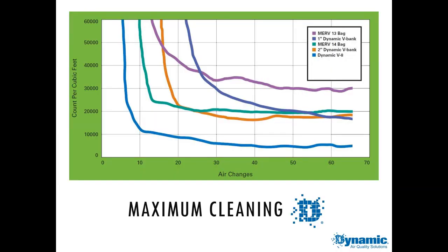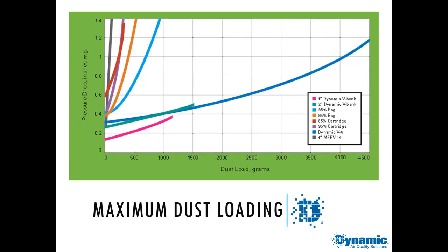So this is a chart that looks at particle counts at 0.3 micron in a recirculating system. Air changes are on the bottom, particle counts on the left, and we do a better job. It looks at MERV 13 and 14 filters, and obviously the V8 is doing a better job more quickly than those products. This is loading as a function of dust held and pressure drop. Various passive alternatives will hold a few hundred grams of dust. The V8 in contrast will hold several thousand grams, and that's what gives us our energy and maintenance advantages.